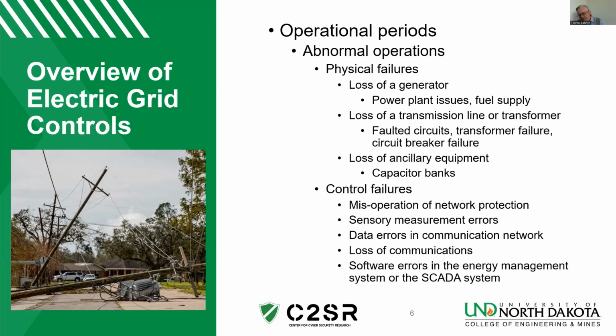SCADA systems play an important role here, but they do have software errors. We've seen utilities like First Energy and others who had problems with their SCADA system software that caused events to take place. And inside of those, SCADA is one of the most important parts of collecting data, but collecting data needs to be reviewed for its accuracy so that a state of the system can be presented to the energy management system. And so we have state estimation, whose whole objective is to use a model of the utility grid and use the sensor data collected over many parts of the grid and check to make sure that the data is consistent.